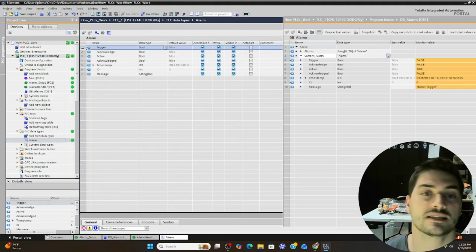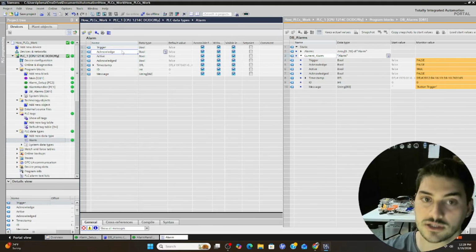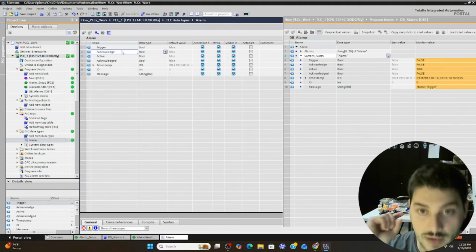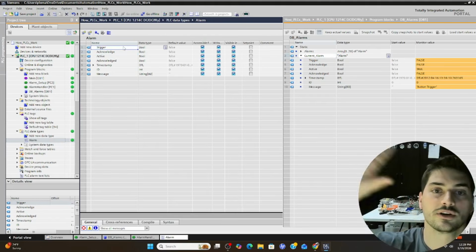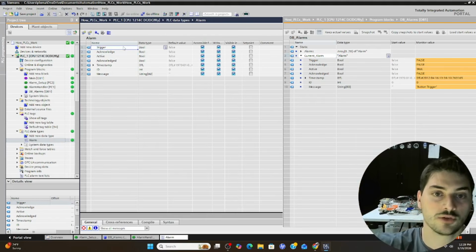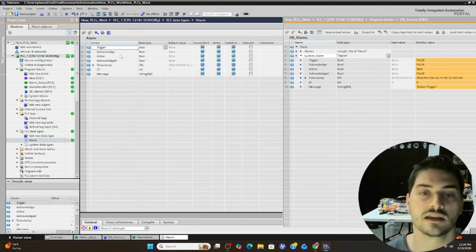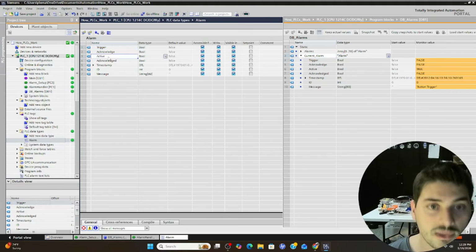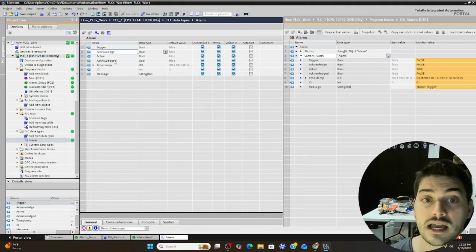You're saying, what does every alarm have? It's going to have some event that's going to trigger it initially, and then it's going to need to give me the option to acknowledge that alarm and say, yep, I've seen it. Because when you trigger an alarm, the most normal response case is that a light would turn on to say, hey, I'm in alarm state. You would shut down the logic until someone had come over and said, I see the alarm, it's okay to resume.